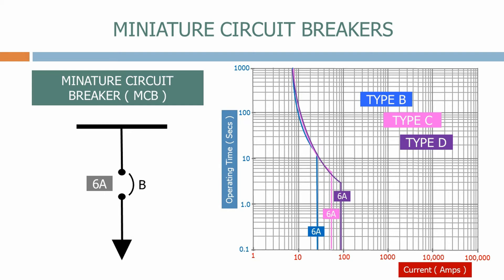For most circuits the type B MCB would be okay but when we are dealing with motors, pumps or transformers that will demand higher current levels when they are switched on we might use a type D circuit breaker.